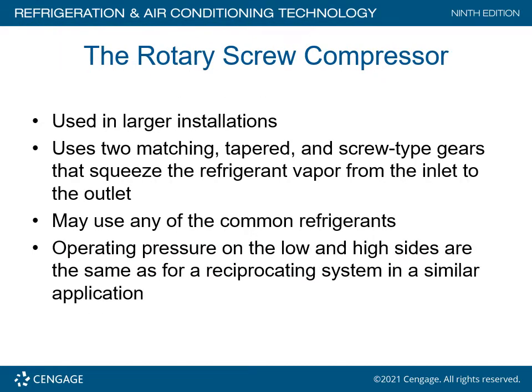The rotary screw compressor is utilized in large installations. It uses two matching tapered screw-type gears that squeeze refrigerant vapor from the inlet to the outlet. It may use any of the common refrigerants, and operating pressures on the low and high side are the same as for a reciprocating system in a similar application.